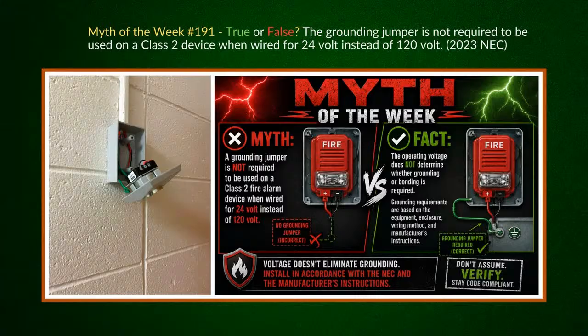It was funny because somebody mentioned if it was a plastic box, then it didn't need a ground jumper. So I'm like, well, does the metal one need one? The manufacturer puts an actual 832 ground screw in there that's not green, so that's the whole thing. It was really hard to get a screw in there because you only had maybe a quarter inch, and it actually bottomed out at the back of the box. So I had to cut that screw exactly perfect to get it to fit in there, and then do a couple extra wraps of ground on there.